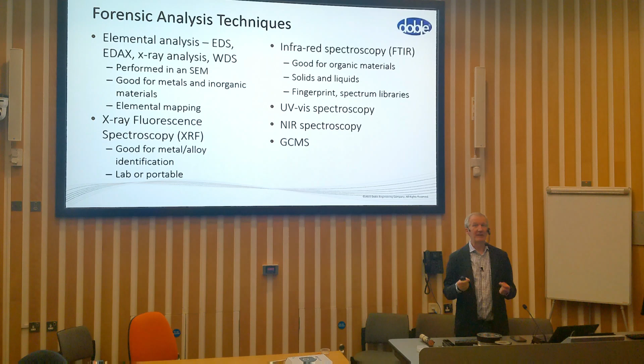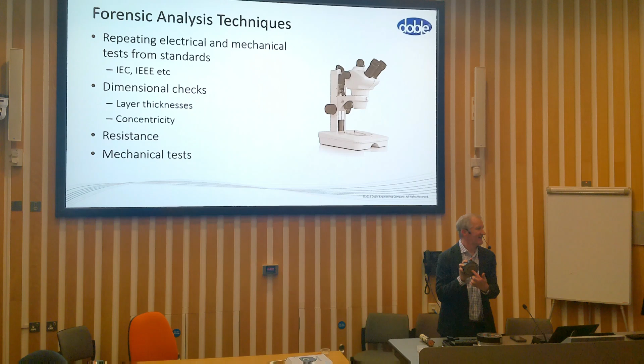And then of course, on some occasions, it's actually just down to the fact that it was manufactured badly. The dimensions are wrong. In principle, the conductor is meant to be absolutely in the center of this. And it's meant to be perfectly round, concentric. The reality, of course, is it never is absolutely perfect. And there are tests in international standards for measuring these things. And sometimes you need to go back and repeat these tests to prove that the cable didn't actually meet the manufacturing specification in the first place. That's always a good start. Get the cable maker on the back foot.